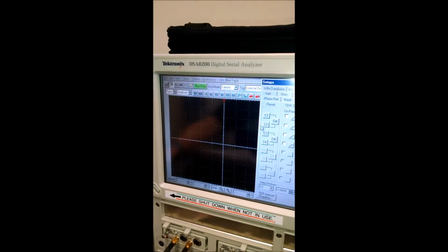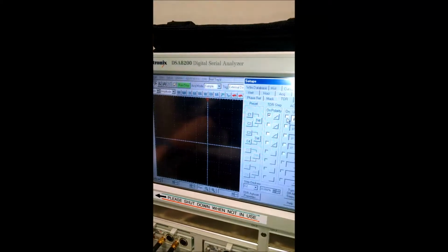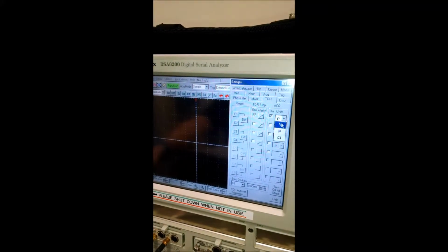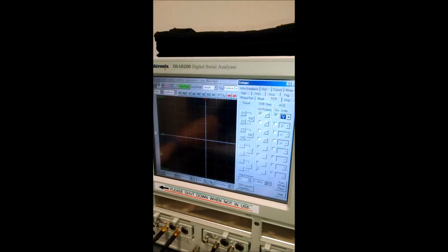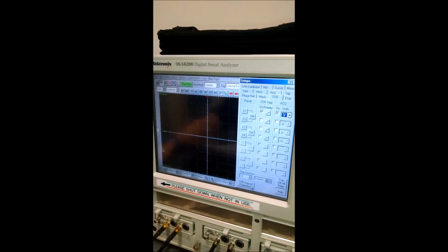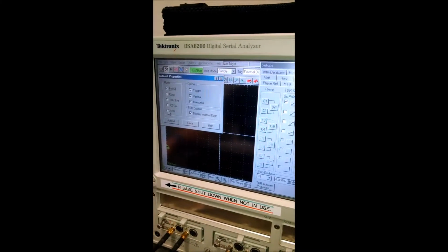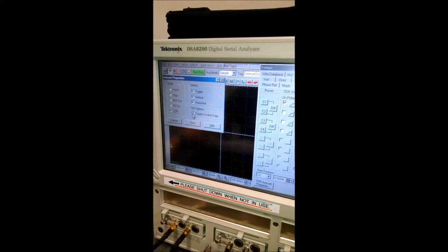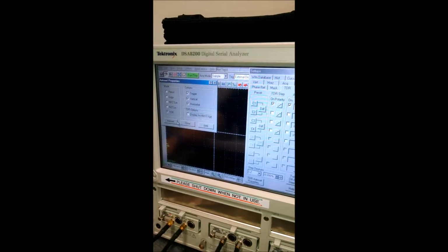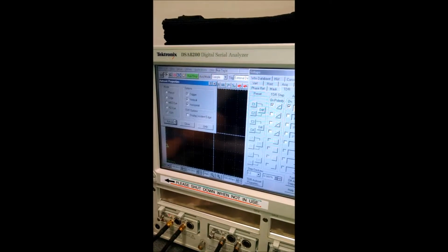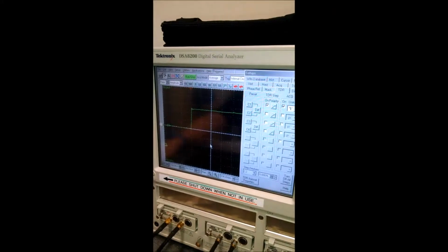Make sure your TDR step is on, acquisition on, and you're measuring voltage. Now, go to your TDR auto setup properties. Make sure you have TDR displayed, and you don't want to display the incident edge. Okay, and press auto set. Okay, you can close that.